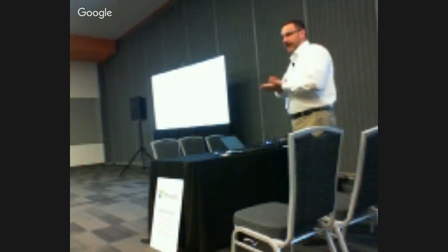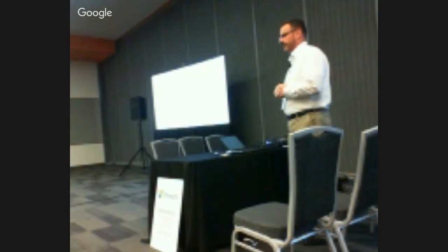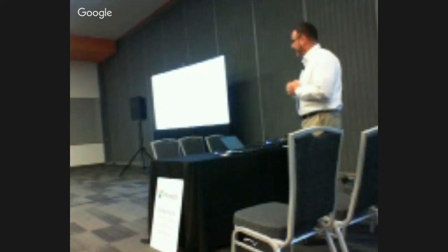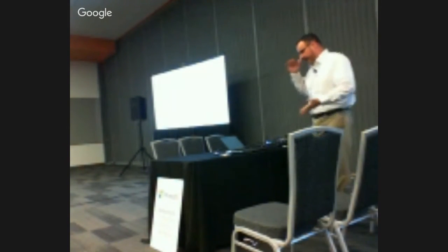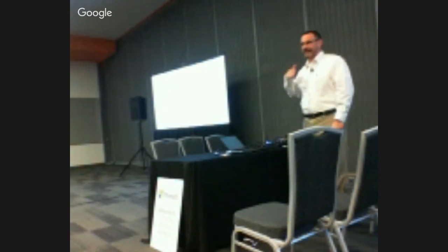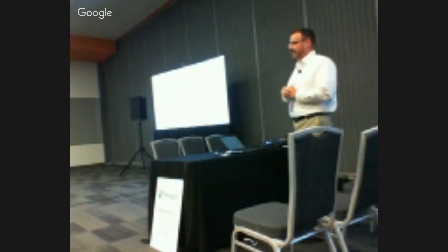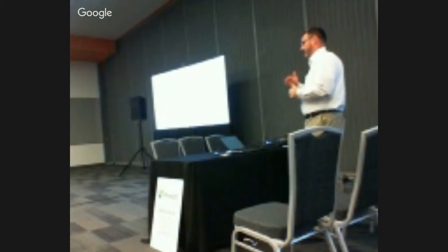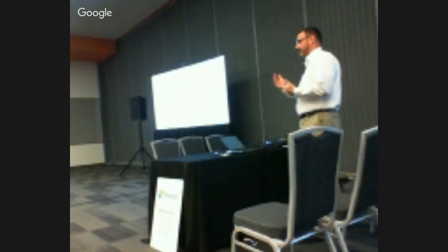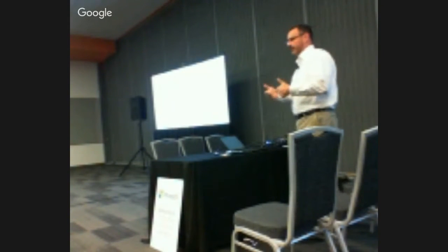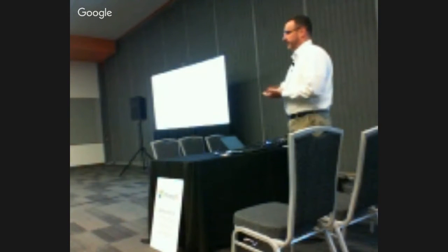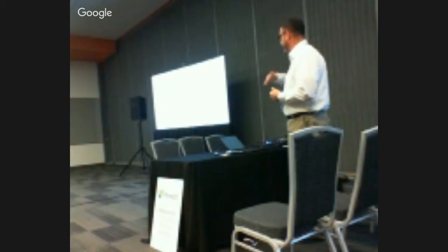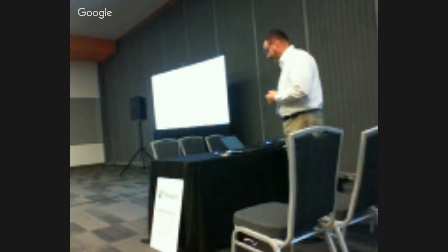Now, how many people here, I like doing little surveys, are involved with very, very large data centers? Okay, great. So depending on the size of your data center, do you design the MV, LV, et cetera? People usually get involved in MV design for data centers that probably minimum is 5 megawatts of IT load. Probably as you get to 10 megawatts is when the designers get involved versus it being provided by the utility. So just understand that if your scope is lower, you can look at LV on down.